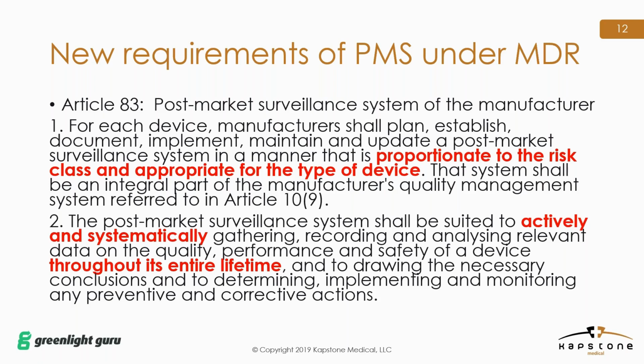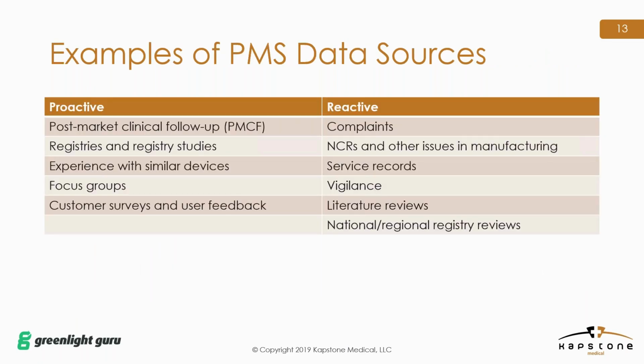As previously mentioned, many companies have performed post-market surveillance activities. However, these have been very much reactive, or in other words, you haven't specifically planned for them. They're just sort of given to you. Some of these common reactive approaches to post-market surveillance have, of course, been complaints, non-conforming reports, or any other issues that you've seen in manufacturing, anything related to service records if applicable to your type of device, vigilance and vigilance reporting, and literature reviews, which is really a reactive approach to post-market surveillance because you're relying on other people's data. And then, of course, review of national or regional registries, which again is reactive because it's out of the control of the manufacturer.